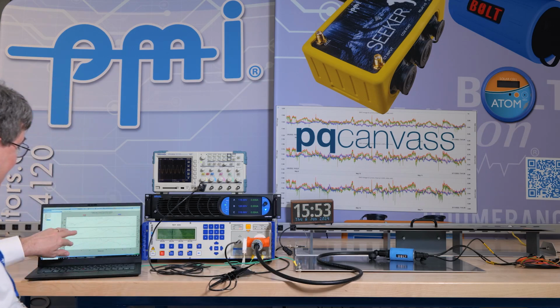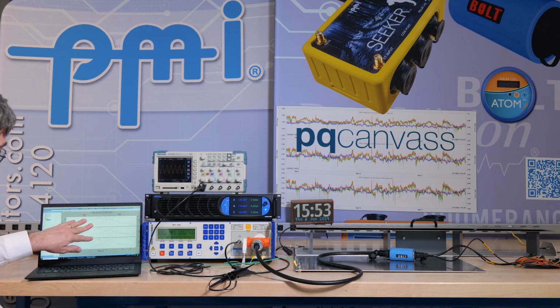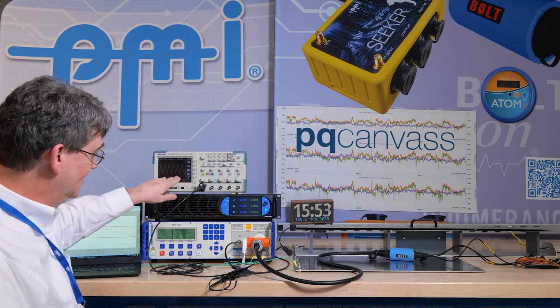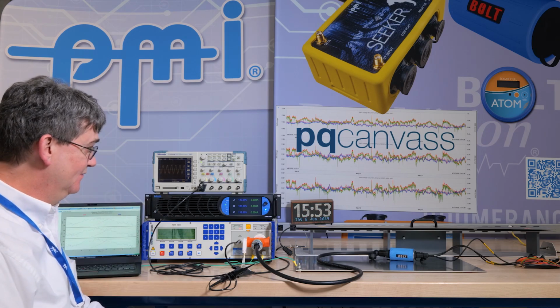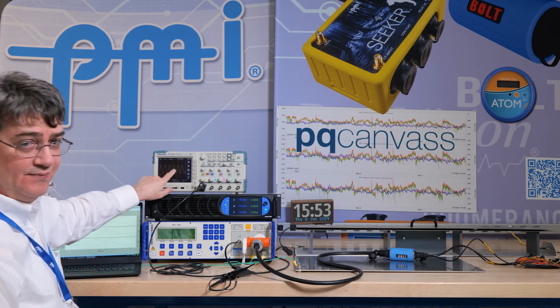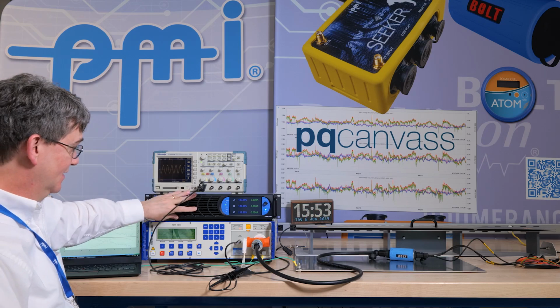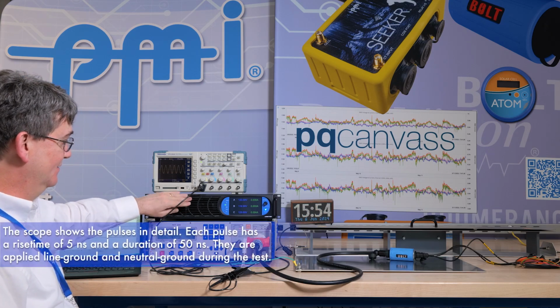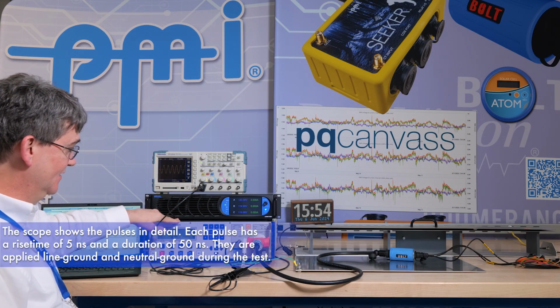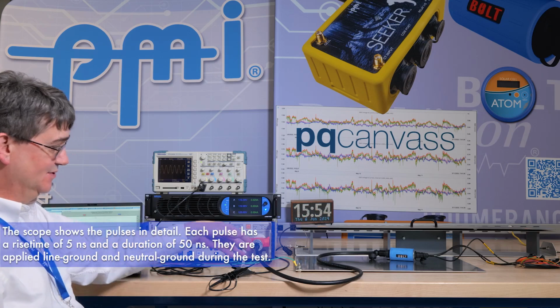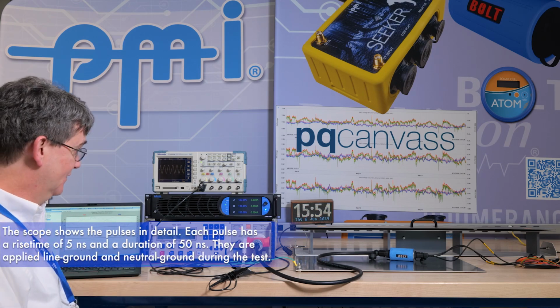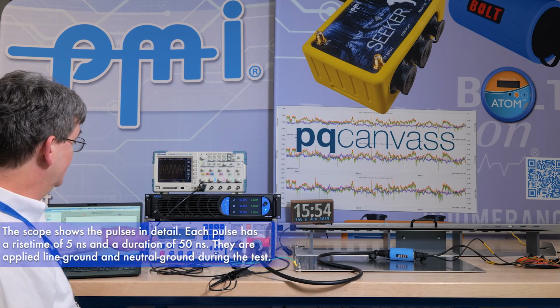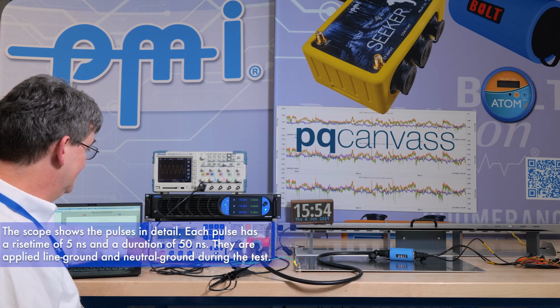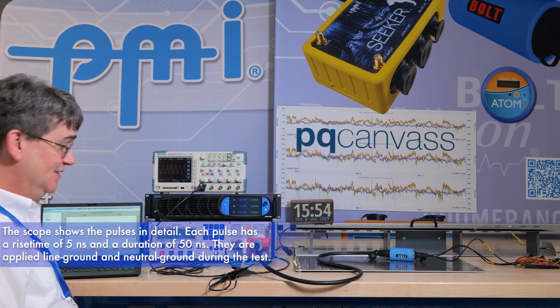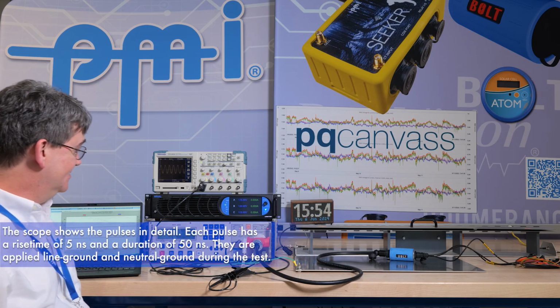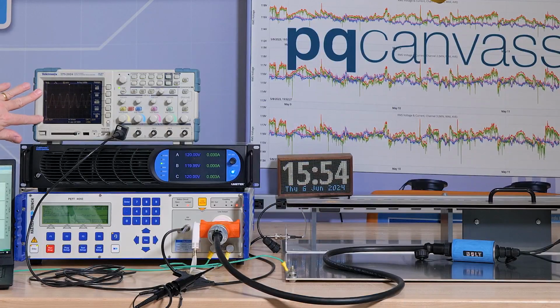And we have a Wi-Fi connection to the bolt now, looking at waveforms, and we have a scope connected in parallel, loosely coupled to this, so that we can see the pulses superimposed on the 120 volt sine wave. We have an AC power supply that is fed into the pulse generator, and the generator couples the pulses onto that 120 volt output. So I'm going to run the test, and the machine takes a few seconds to warm up, and then it will start applying these pulses, and we can see these on the scope when it starts.